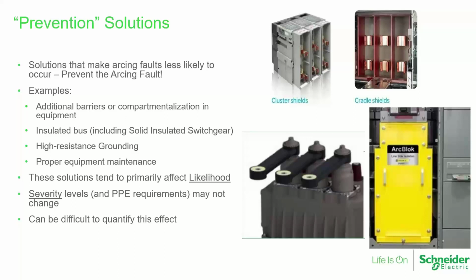Even things as simple as high resistance grounding can be a potential prevention method. High resistance grounding, the idea being that you significantly limit the energy that's available in a single line to ground fault. If you only have 5 amps flowing, if you have a ground fault, then it's much less likely to escalate into a 3-phase fault that could be a much more explosive event.